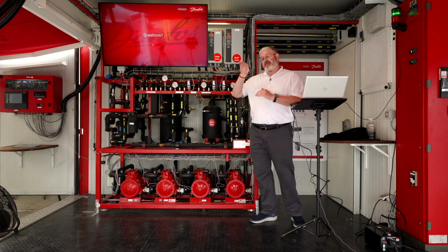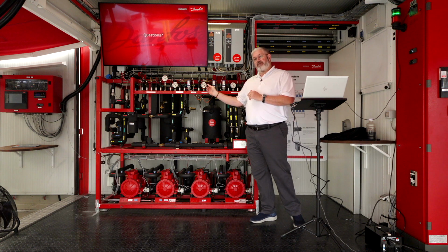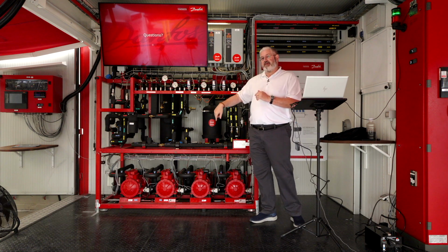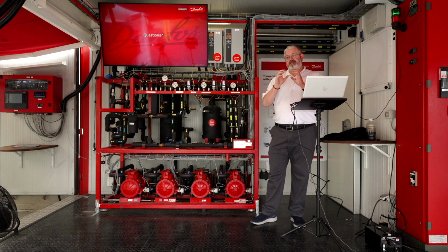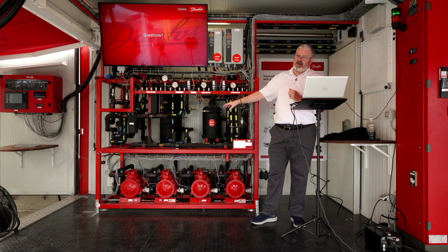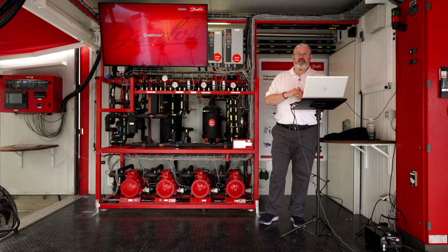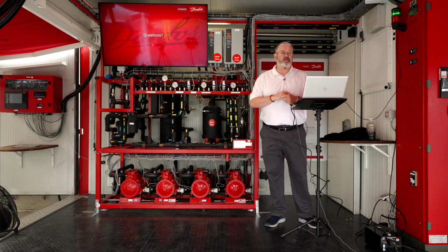The flash gas is on the top of the tank, and we take that vent off the top, and that's what gets diverted to the medium temp suction. So the medium temp suction is taking that around the evaporators. It's all done here at the system. The evaporators will all get 100% liquid, both medium and low temp.